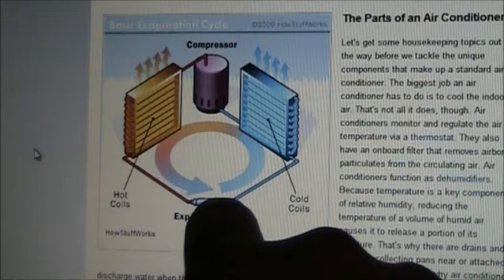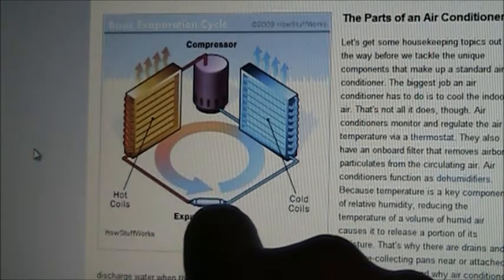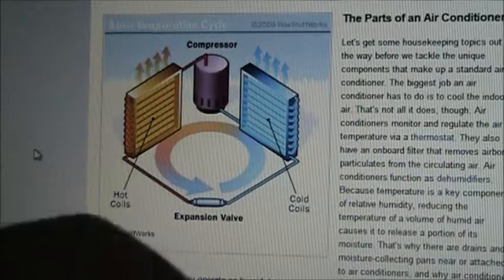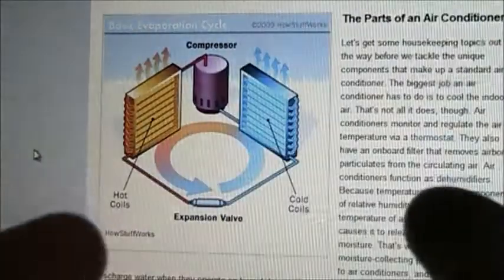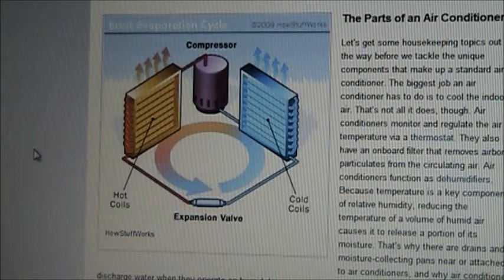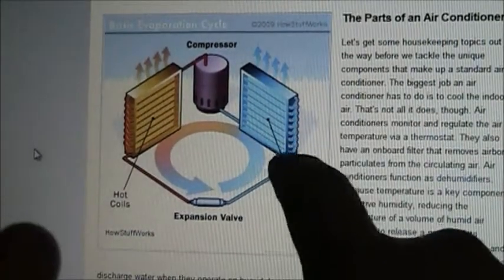Once it comes out of the expansion device, out of the capillary tubes, which are about that big around, I mean, they're pretty small, it's going to come out of that and then go into the evaporator coil tubes, which are about that big around, which is much bigger. It's going to evaporate or expand into a vapor very fast, which makes it extremely cold, which is how the evaporator coil gets cold. It's going to be a liquid evaporating into a vapor the whole time that it's going through this coil, which is why the evaporator coil is cold.